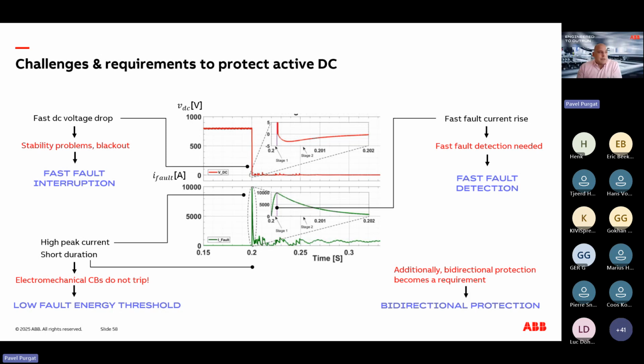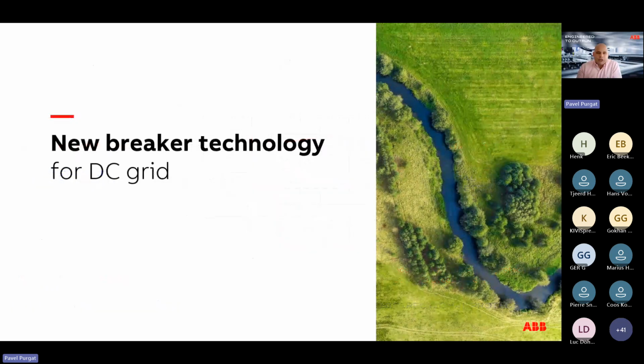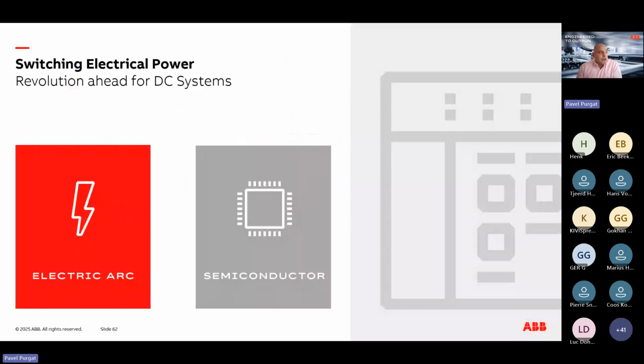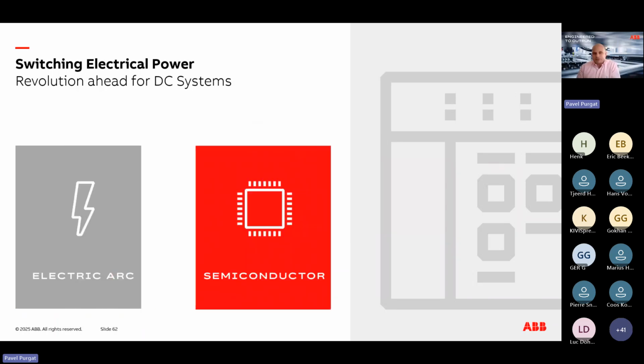And as I explained, bidirectional protection becomes a requirement in DC because we want to, for example, recuperate the energy. But if we put unidirectional protection, then we don't have control in both directions for protection, and it becomes, again, dangerous. So for all these reasons, we also need some new technology for protection of DC grids. And the technology is essentially, instead of using an electric arc to extinguish the short circuit, to go to semiconductor.